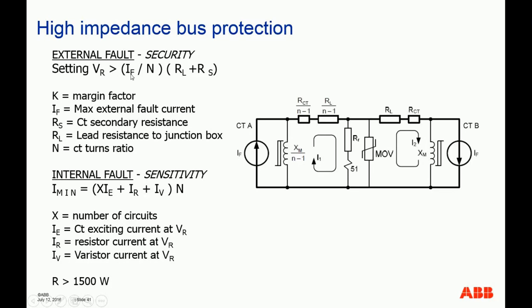So you have your setting calculated as your full fault current divided by your CT ratio, that's your secondary current, multiplied by the total resistance of the CT lead and also the winding. And then you will add the margin. Rest assured that through a calculation like this, this will be the maximum voltage that this circuit can ever experience during an external fault. Only an internal fault could create a voltage higher than this. So it's very secure, because we know that during an external fault, no matter how badly the CT saturates, because we already assume the worst scenario, no voltage can be higher than this, plus margin.